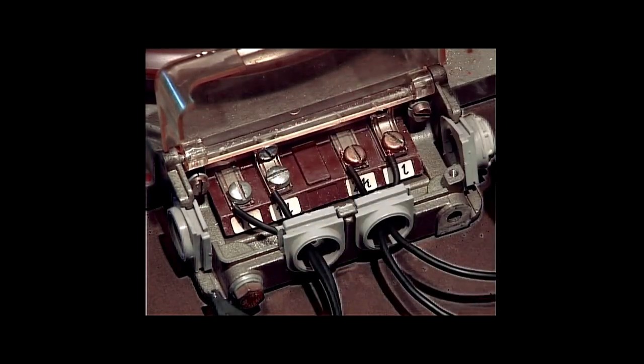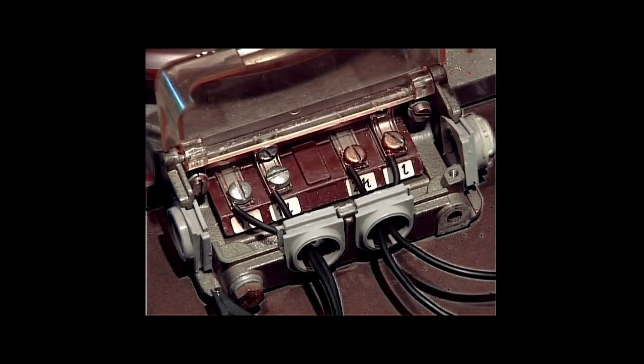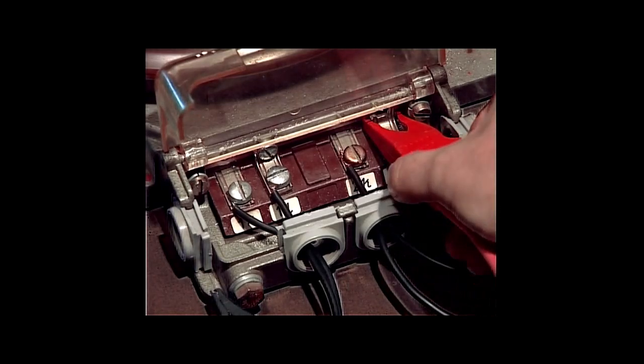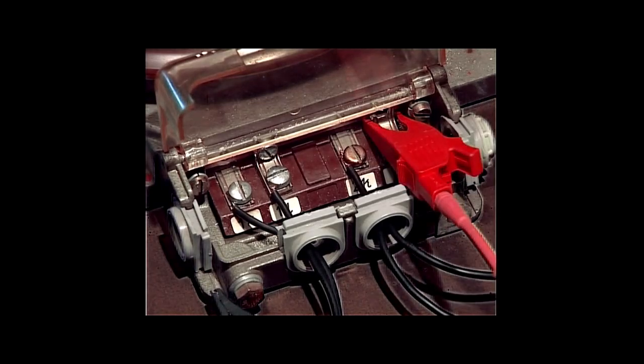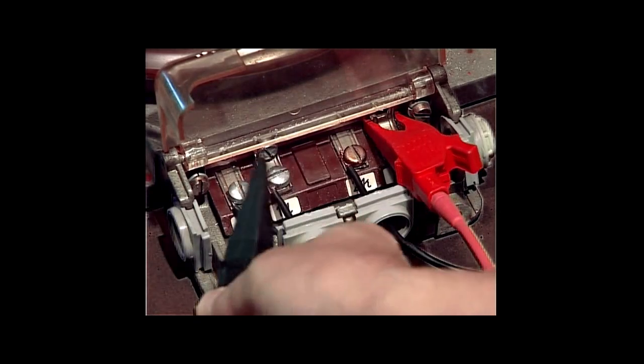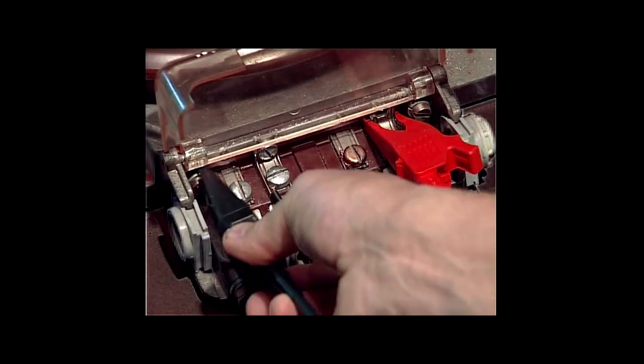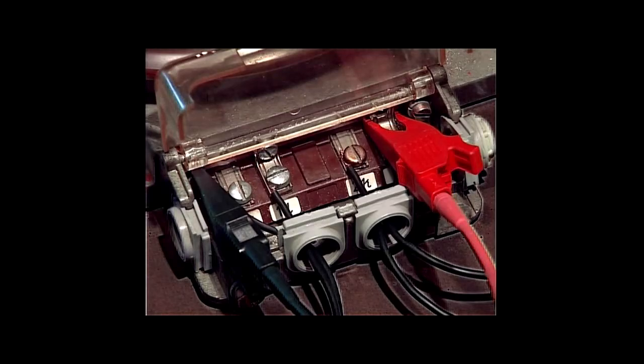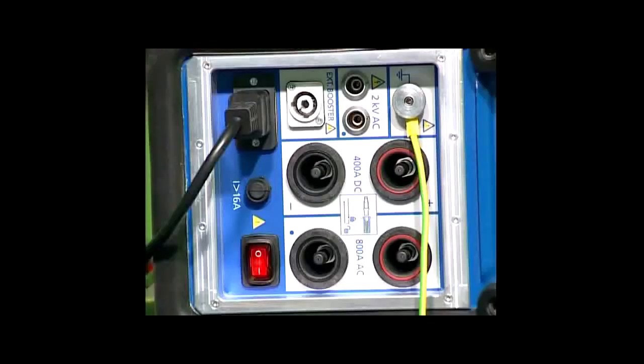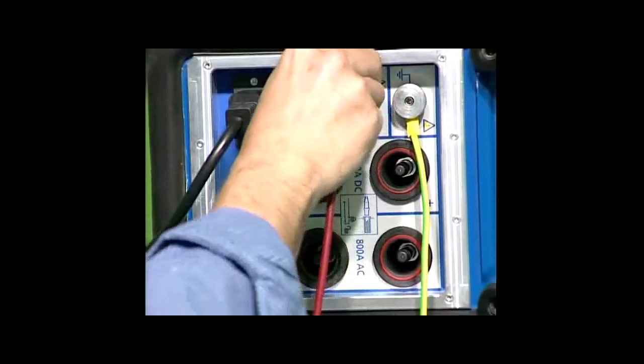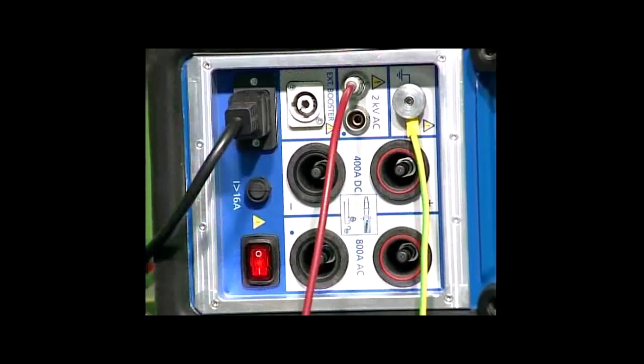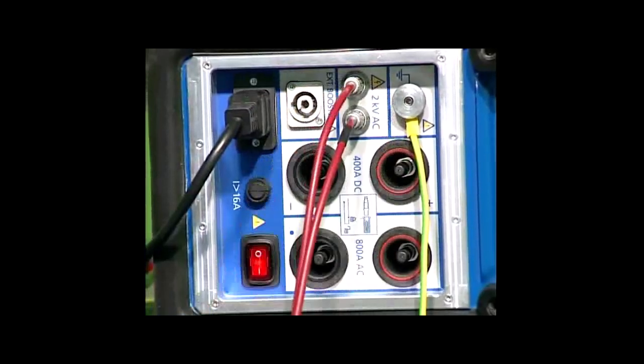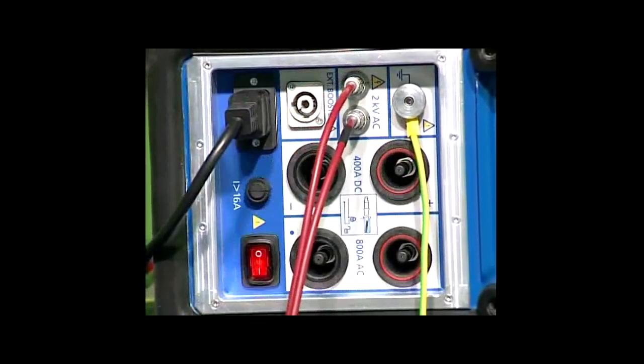The high voltage source built into the CPC allows for a voltage withstand test up to 2 kilovolts. Thus, the voltage withstand capability of the secondary wiring of CTs and VTs can be tested.